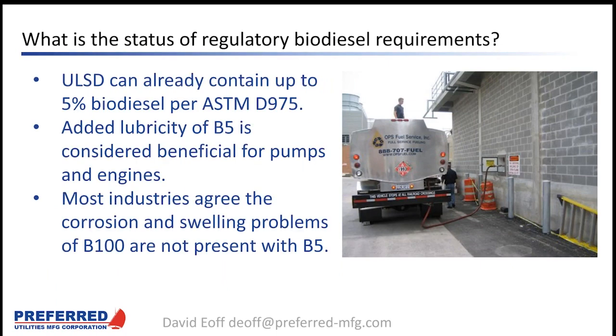So what is the status of regulatory issues with biodiesel? Most ultra-low sulfur diesel already contains biodiesel. ASTM D975, which is the standard for ultra-low sulfur diesel, allows up to 5% biodiesel and the provider typically isn't required to disclose the biodiesel amount in the fuel. Several states, however, require that fuel delivery companies disclose how much biodiesel is in each truckload or each delivery, but that's a state-by-state requirement.